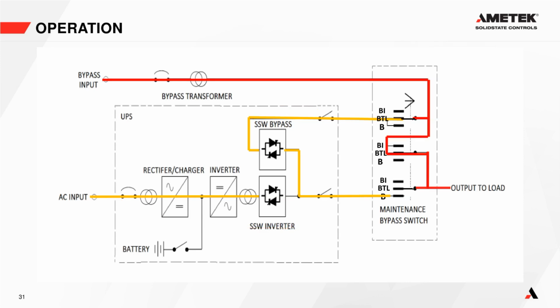And in this situation, if you had an AC input failure and you were hoping to go to battery, you're going to lose your load, because if the AC input and the bypass input fails, the battery has no way, because we've opened this switch here, to get to the loads whatsoever. So once you move the maintenance bypass switch to the bypass to load position, you are on bypass, and that is it. You have to rely on that bypass supply.